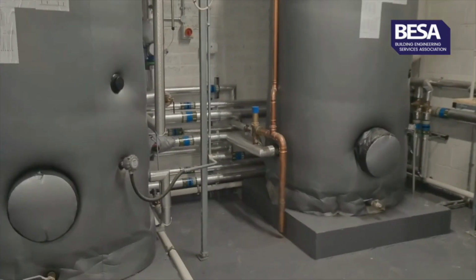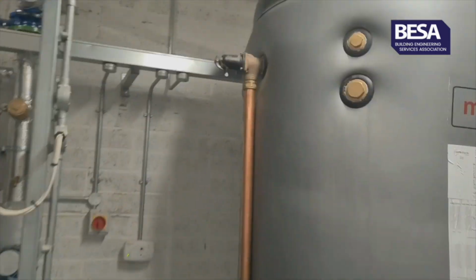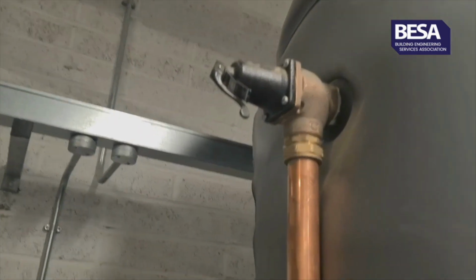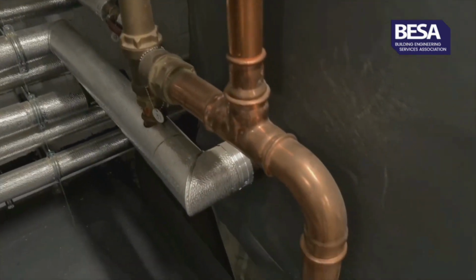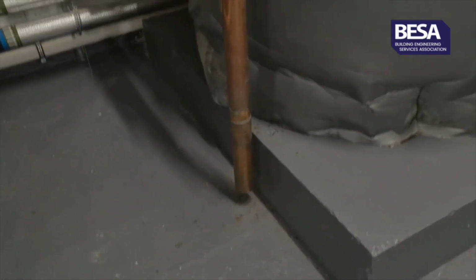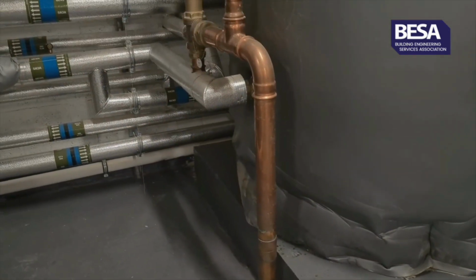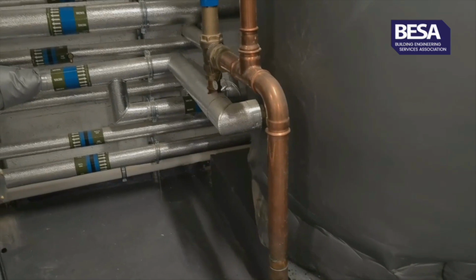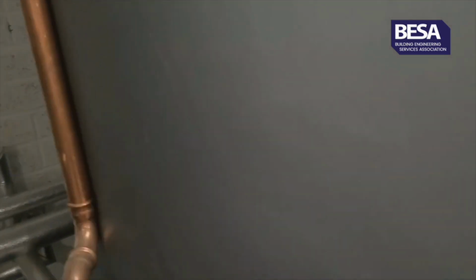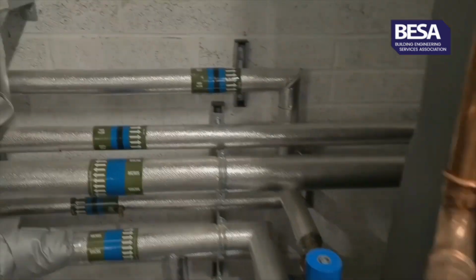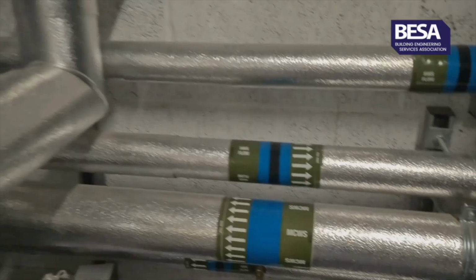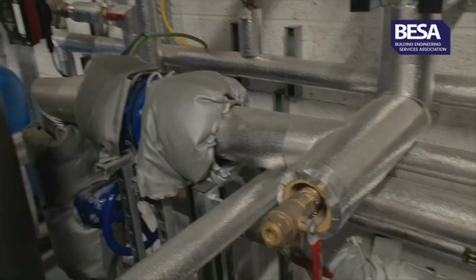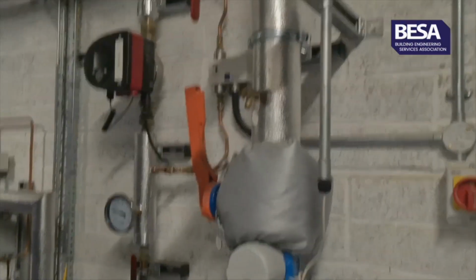Again, if you look at these buffer vessels here, we've got safety discharge valves, all in copper pipe work, and then all the way down to the ground. Again, all WRAS approved. The proprietary insulation jackets are all fitted as well. All pipe work's been insulated, overclad, and ID'd as well. And hopefully no open ends.